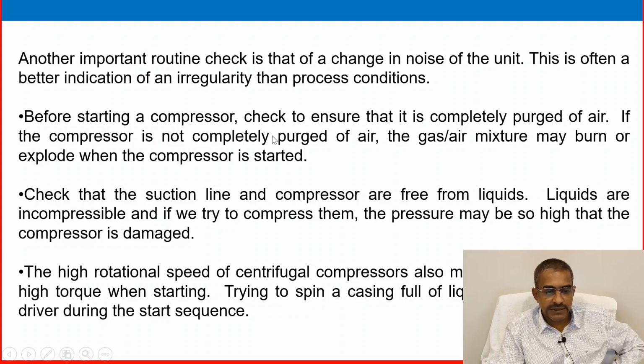Before starting the compressor, check to ensure that it is completely purged of air. If the compressor is not completely purged of air, the gas-air mixture may burn or explode when the compressor is started. It's very, very important. Check that the suction line and compressor are free from liquid. Liquids are incompressible, and if you try to compress them, the pressure may be so high that the compressor is damaged.